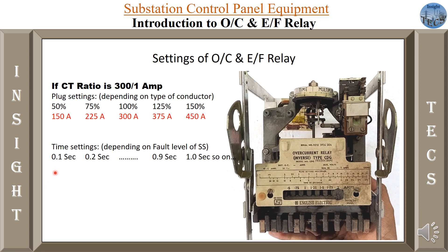The second setting is the time setting multiplier, which can be set to 0.1, 0.2 seconds and so on. When 150 amperes flows and the disc starts rotating, within 0.1 seconds the contact will be closed — the plunger will operate and change the NO to NC contacts, sending the trip command to the breaker or master relay. According to the IDMT curve and the requirements of the system, we have to set the time settings based on the fault levels of the substation. Higher the fault level, the time setting will be done accordingly.